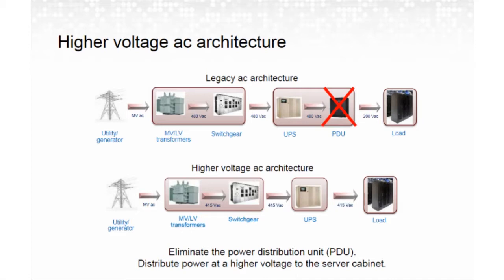When you look at the server cabinets or computer voltage, the power supplies actually have a voltage range between 100 and 240 volts. That was basically done so those components could be used here in the U.S. at the 120 or overseas in Europe and Asia at the 230 volt, so they didn't have to change components. So the intent is to utilize that higher voltage range and distribute the power at a higher voltage, say 415, right at the UPS straight to the cabinet. So you're basically eliminating that transformer, eliminating the impedance associated with it.